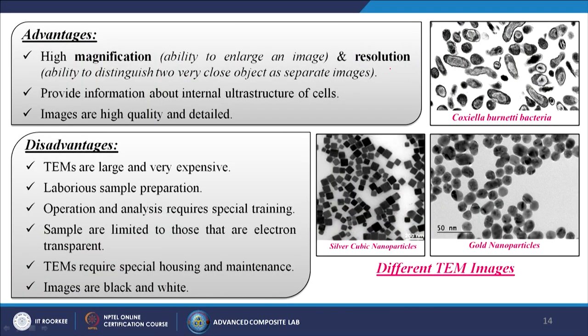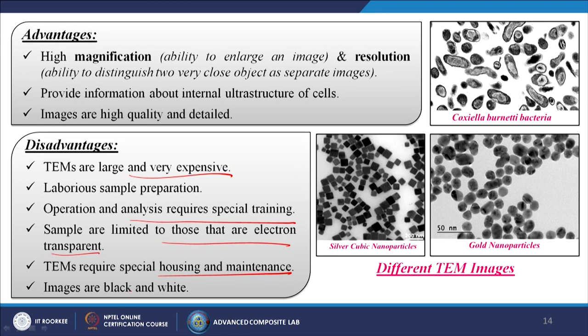Advantages of TEM: high magnification, ability to enlarge an image and high resolution to distinguish two very close objects as separate images. Provides information about internal ultrastructure of cells; images are high quality and detailed. Images can be obtained at 50 to 200 nanometer scale, such as silver cubic nanoparticles, gold nanoparticles, or bacteria. Disadvantages: TEMs are large and very expensive, sample preparation is laborious, operation and analysis require special training, samples are limited to those that are electron-transparent, TEMs require special housing and maintenance, and images are black and white.